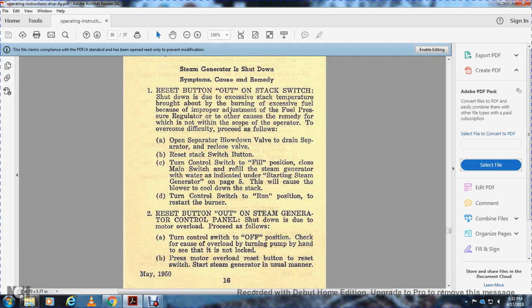B, 2. The reset button out of the steam generator control panel, shutdown is due to motor overload. Proceed as follows. Turn the control switch to the OFF position. Check for the cause of the overload by turning the pump by hand and see that it is not locked. Press the motor overload reset button, reset the switch, and start the steam generator in the usual manner.